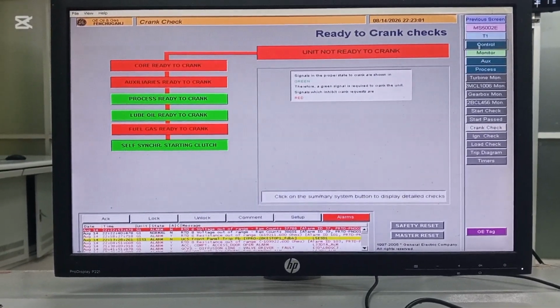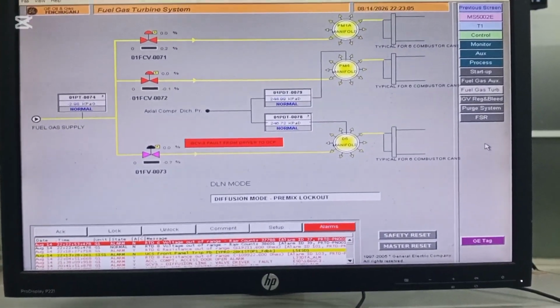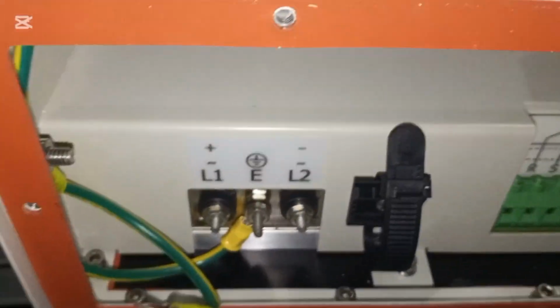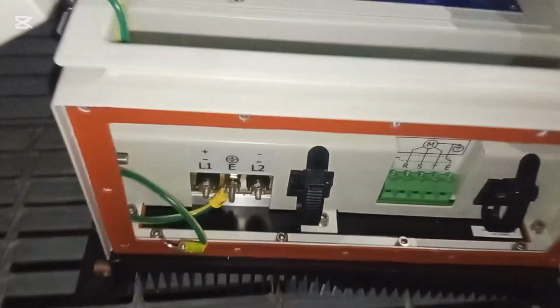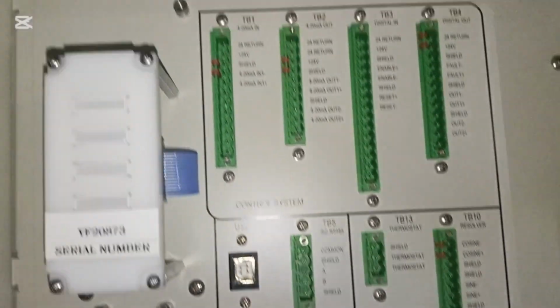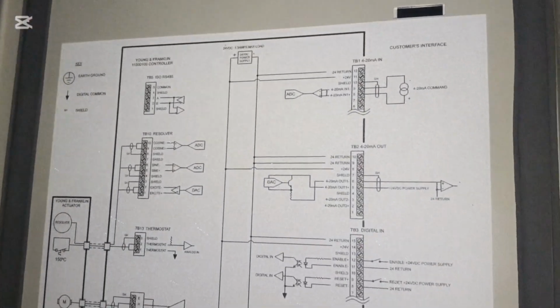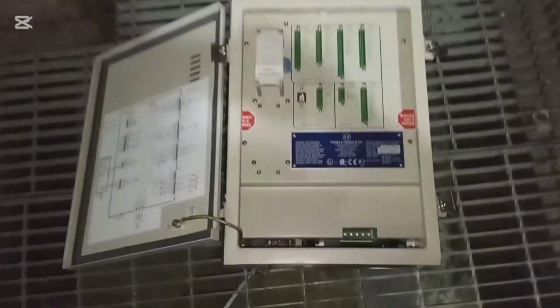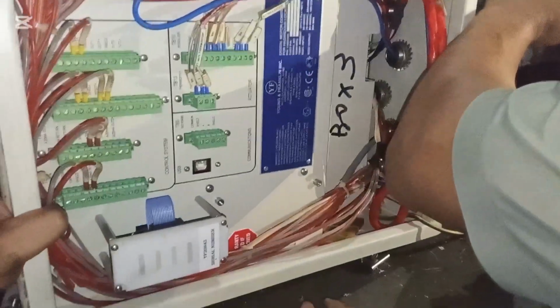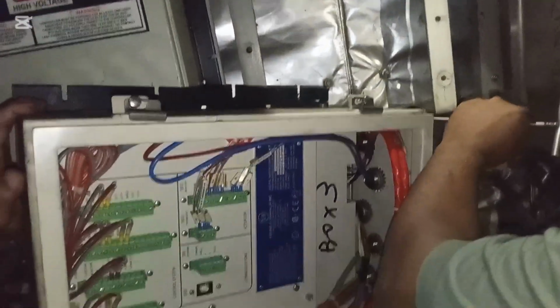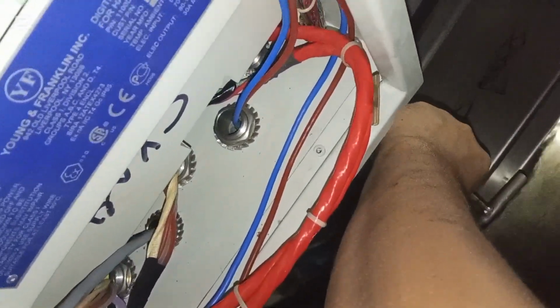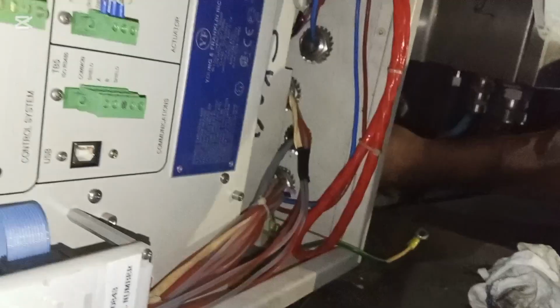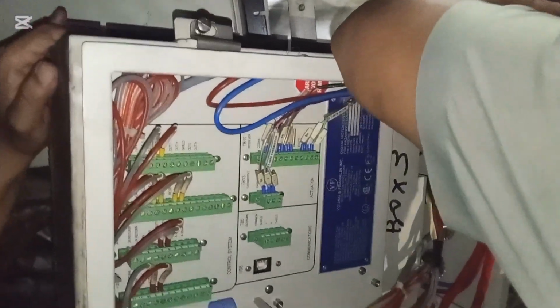We recorded the different alarms from the HMI, and after that we dismantled the base connection of the motor drive controller unit, and all the cable connections are open. This is a new one. This is the new unit which was stored in the store. The cable connector is also present here. We tried to open the cable with connector from the old unit to shorten the maintenance work, because if we open all the connections from the connector, then the work will be too lengthy. For this, we opened the complete cable with connector.